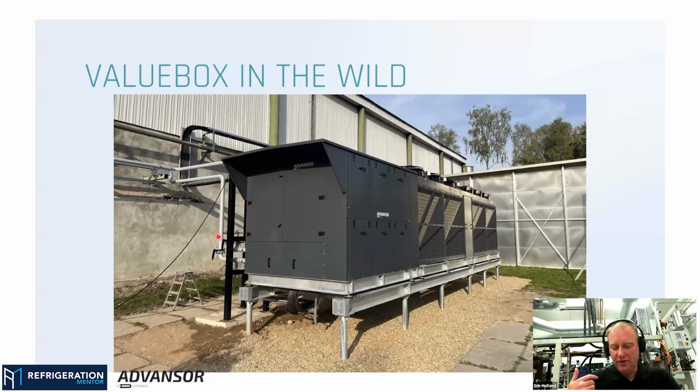Yeah, that would be, for your refrigeration systems, a parallel system to your high pressure valve. So as soon as the system sees that we have enough flash gas for running the IT compressors, then we start up the IT compressors, and we shut the high pressure valve, and then we can start using the ejectors at full effect, because now we can remove all that flash gas we are getting from the ejectors, but we also lift all this liquid from the low stages, and thereby we can maybe stop one or two of the MT compressors.